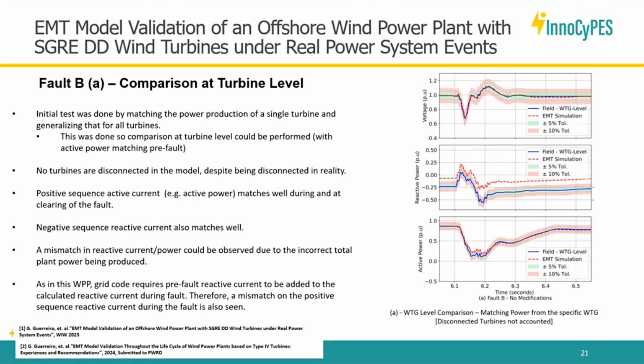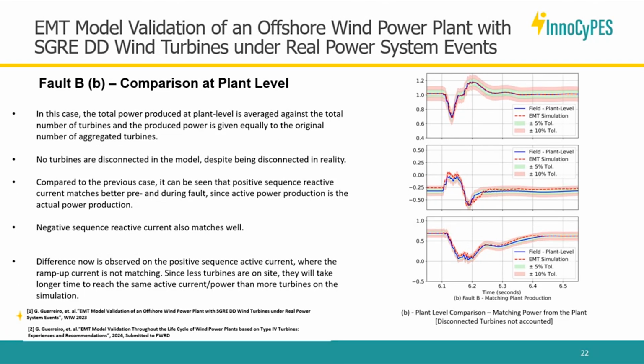That was one of the cases. Then what we did is calculate the whole active power production of the plant and put that through the model. The problem is that we didn't account for the turbines that were disconnected prior to the fault — we simply divided the total power production by all the turbines in the model. Now there is a better match of reactive power, but the ramp-up of active power no longer matches, because when you have more turbines you can ramp up active power faster than when you don't have as many.